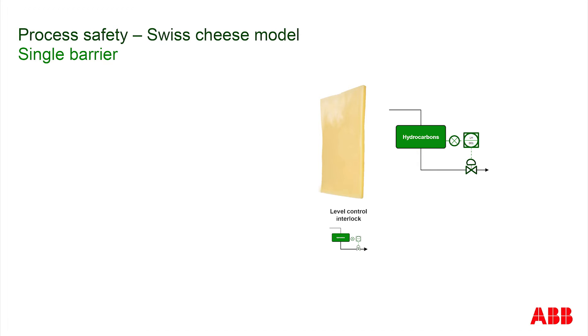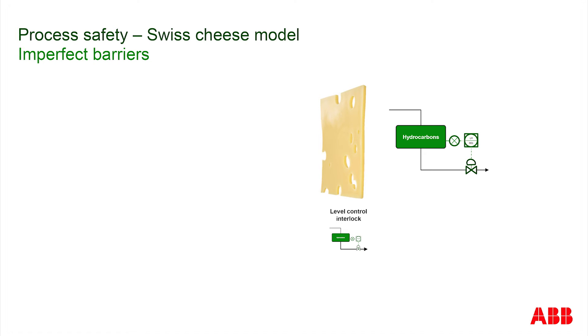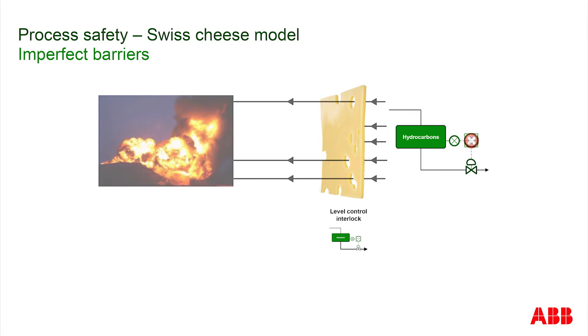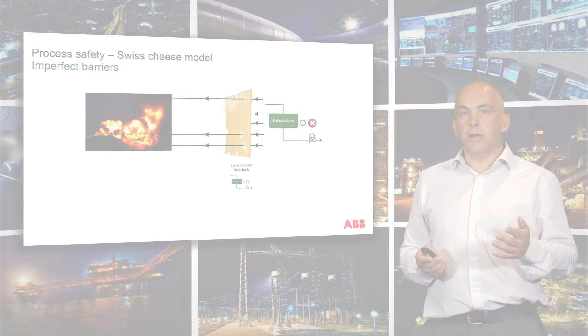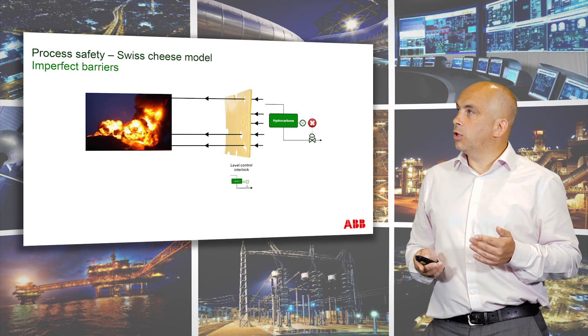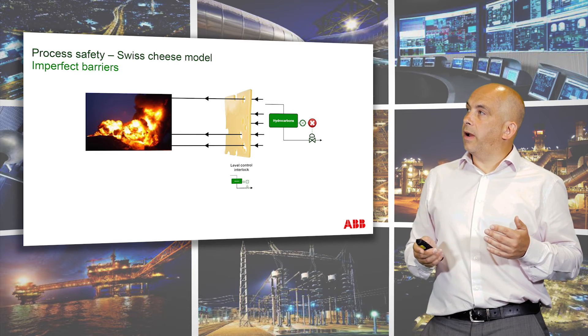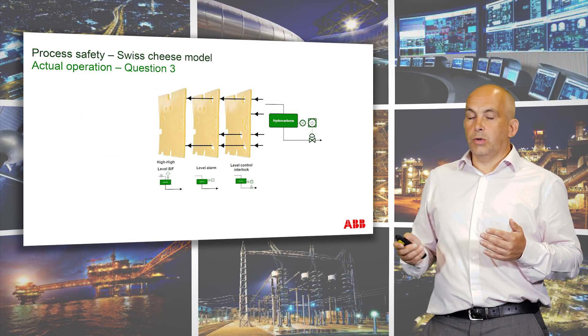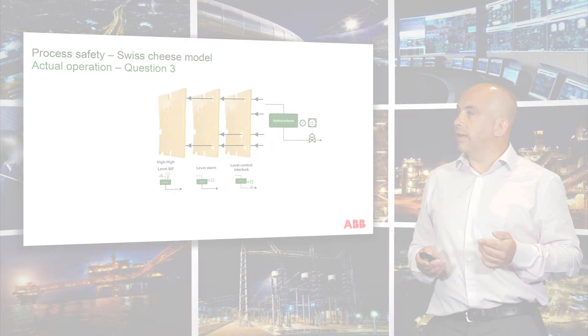Now when we have that failure on the level controller, we don't get the incident. Unfortunately, barriers aren't perfect. They've got holes in them, hence Swiss cheese. Now when we have the failure, we lead to the event. That's why we never rely on a single barrier. So we put in place multiple barriers and no single failure can lead to the event.